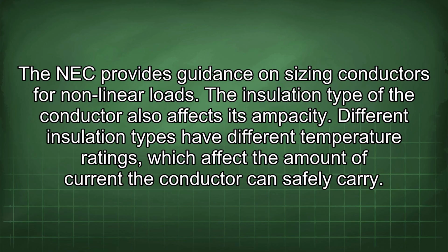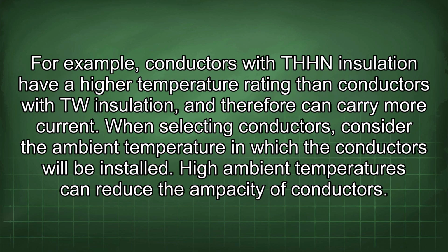The insulation type of the conductor also affects its ampacity. Different insulation types have different temperature ratings, which affect the amount of current the conductor can safely carry. For example, conductors with THHN insulation have a higher temperature rating than conductors with TW insulation, and therefore can carry more current. When selecting conductors, consider the ambient temperature in which the conductors will be installed.